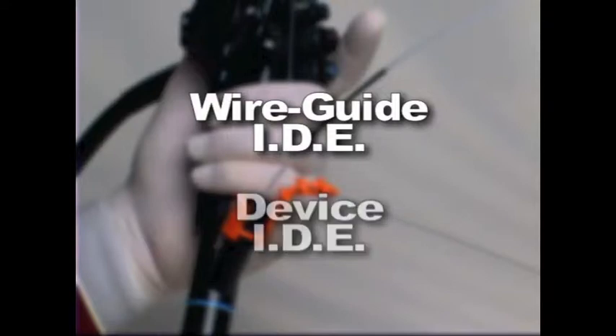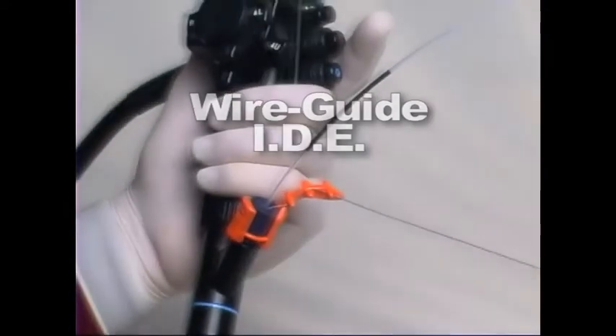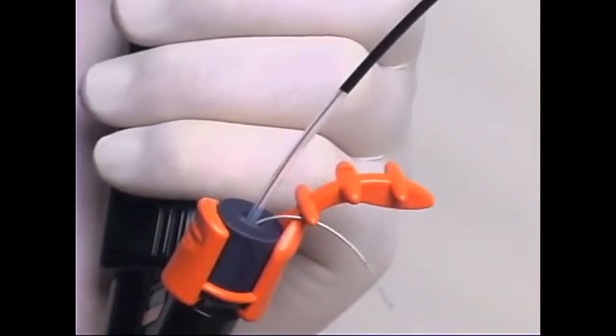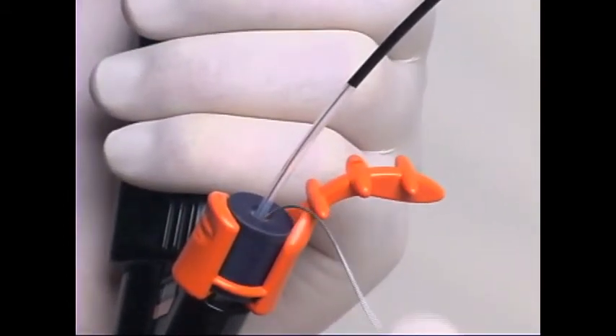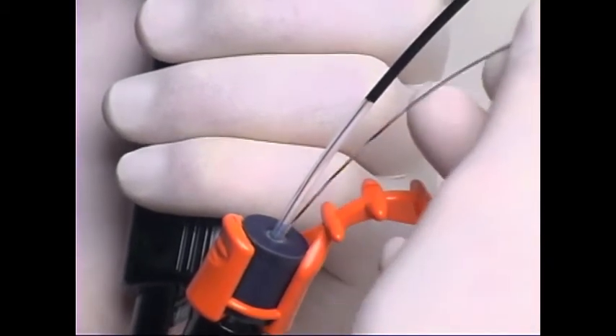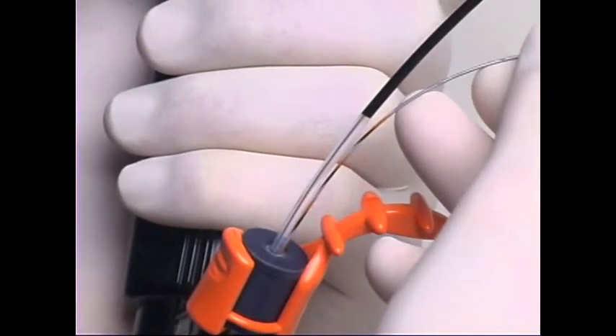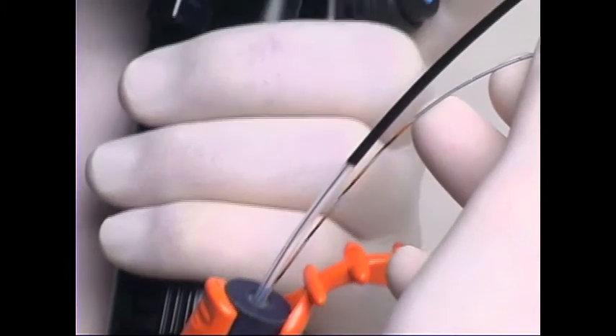There are two options for intraductal exchange: the wire guide IDE or the device IDE. For the wire guide IDE, disconnect the wire guide from the wire guide locking device. Then slowly pull back on the wire guide. For visual reference, the proximal portion of the wire guide and the proximal portion of the device catheter are color-coded. When the IDE reference marks on the wire guide reach the distal end of the catheter IDE reference mark, the wire guide is even with the end of the catheter.